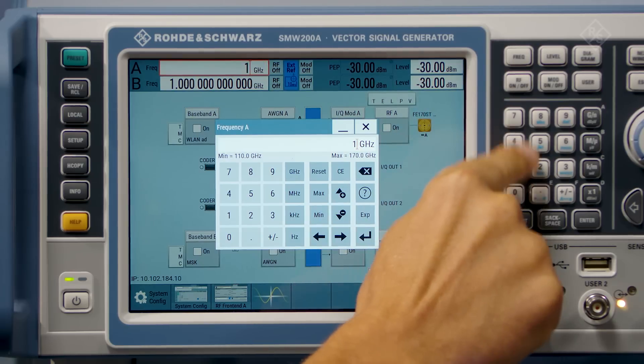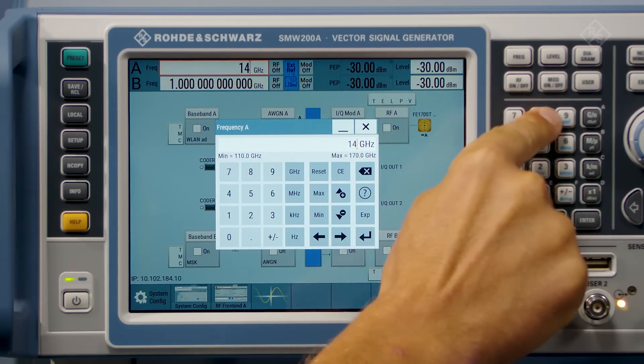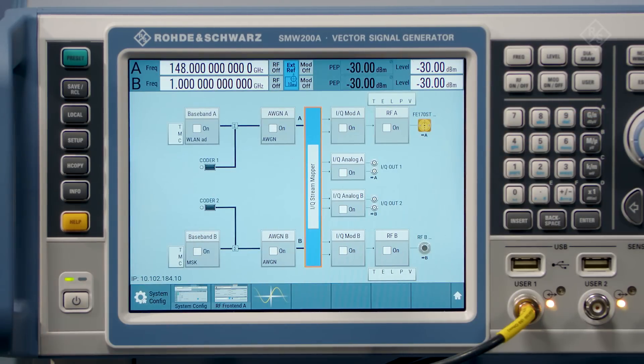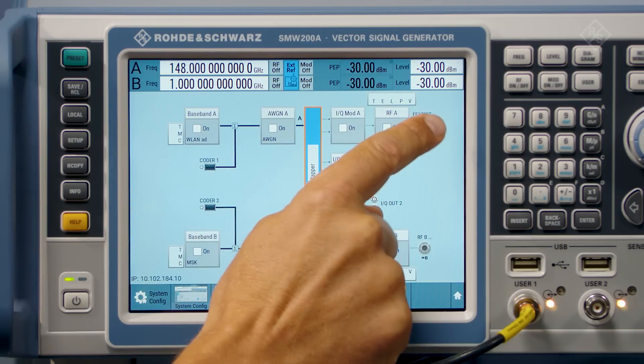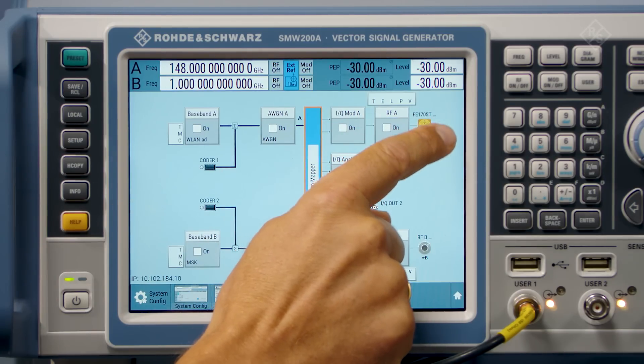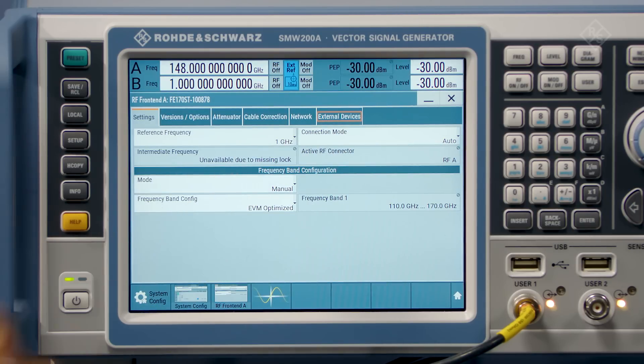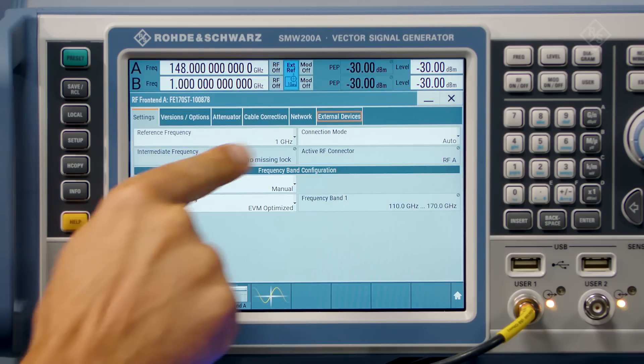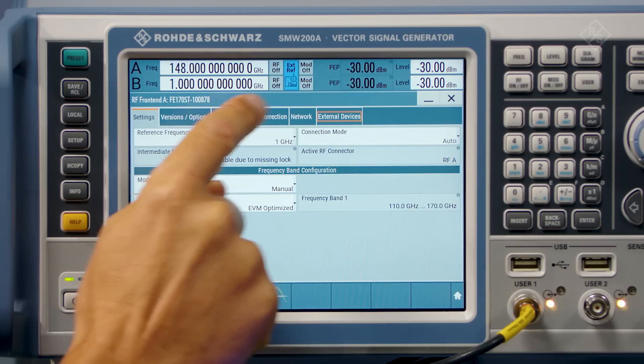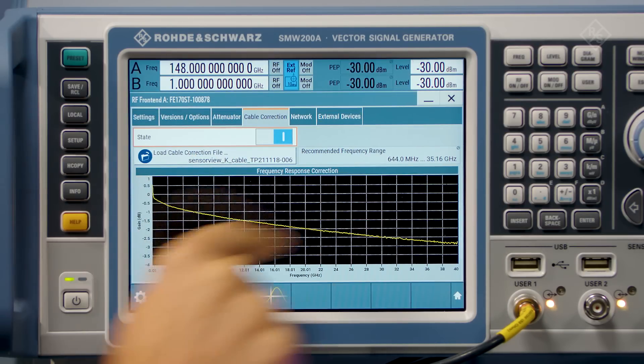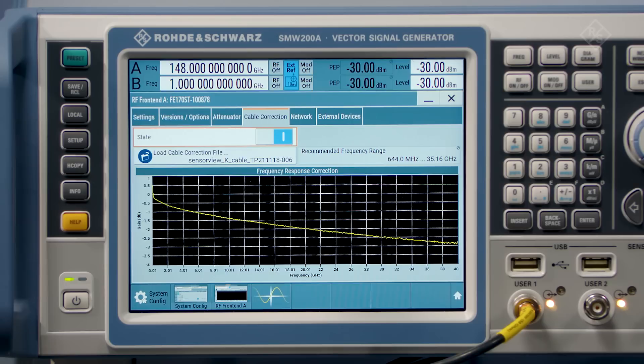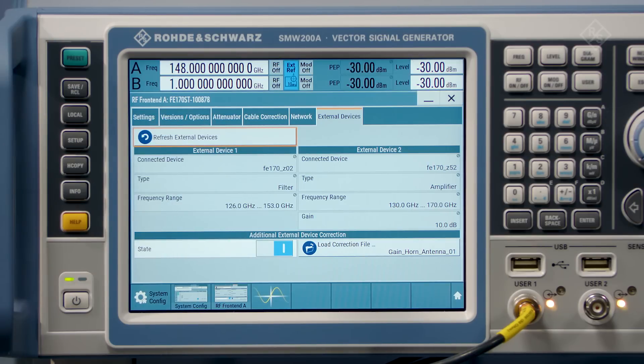For the demo, I set the frequency to 148 GHz. It can also be seen that for the RF connector, the icon has changed, and once I click on that icon, we come into the menu for the more detailed configuration of the frontend — for example, configuration of the reference frequency or to compensate the IF cable, where a correction data can be loaded. More information on the connected external devices can also be found here.